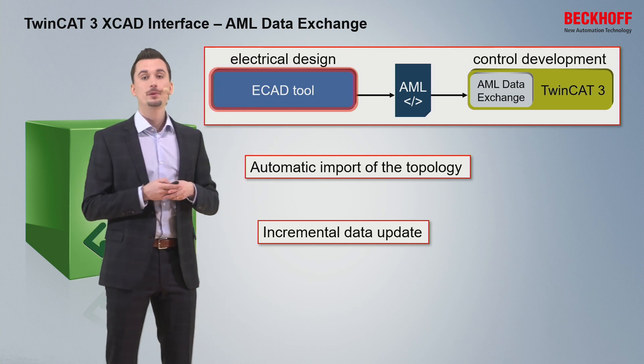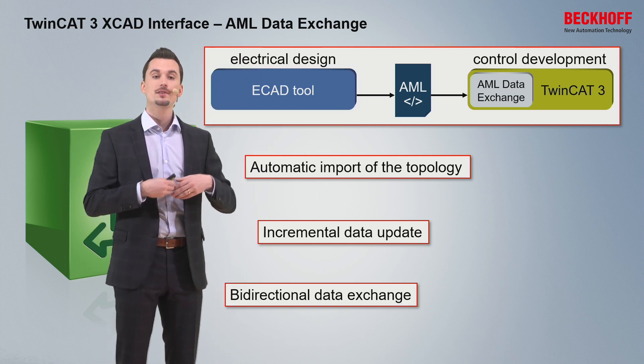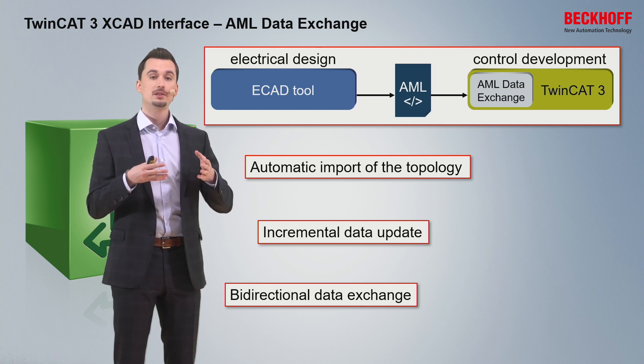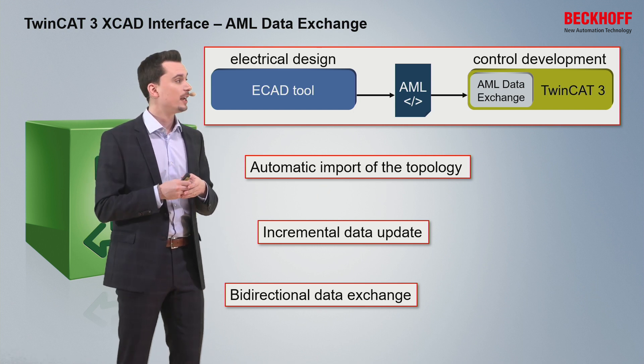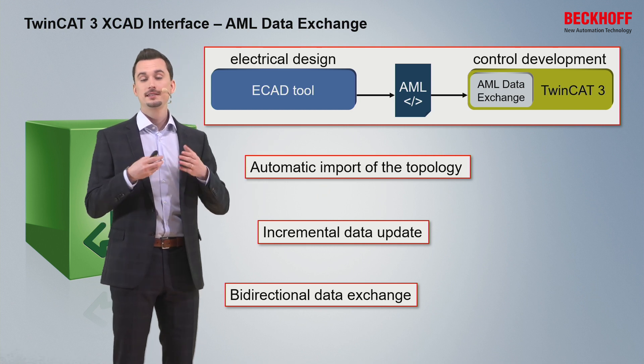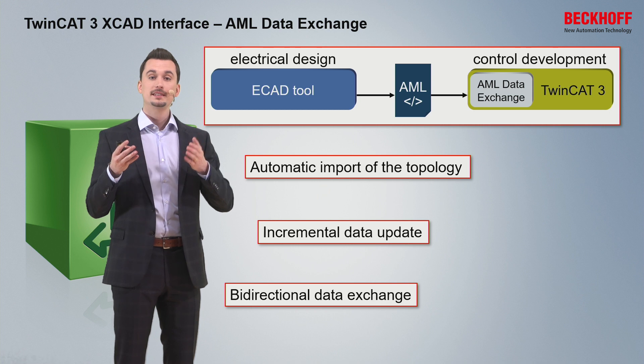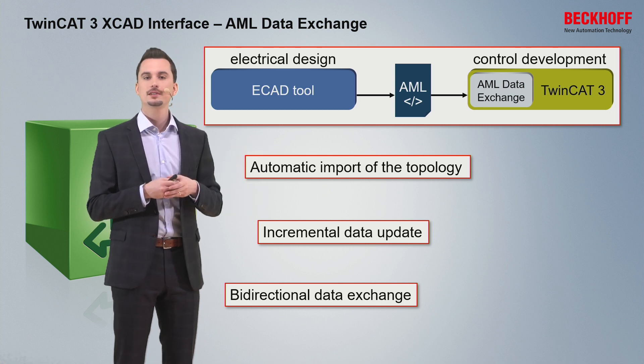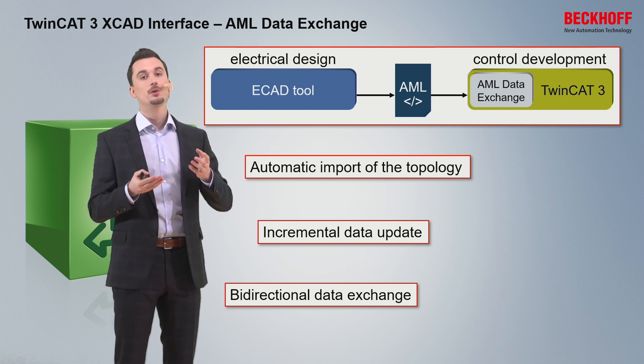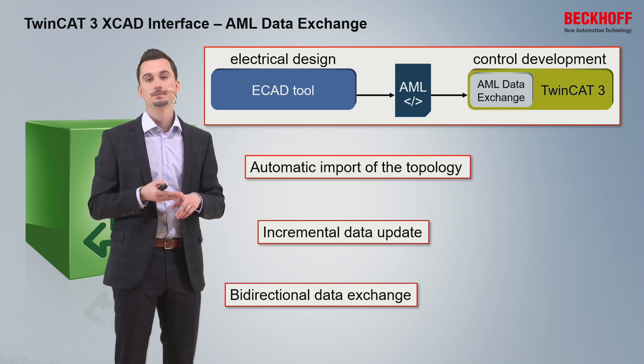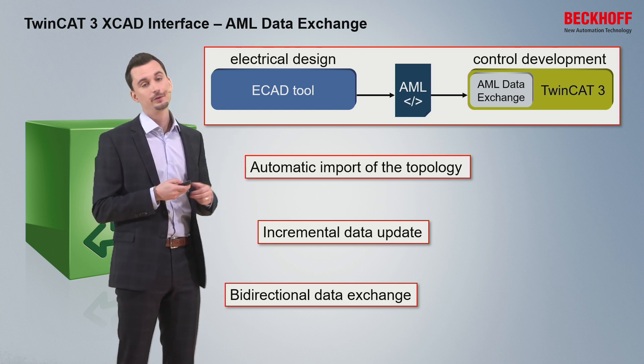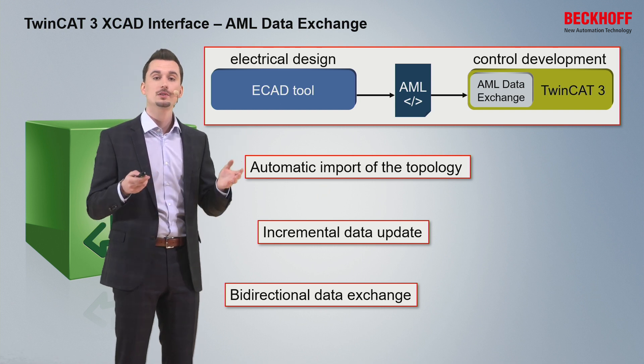At a later stage in your project, you can also use the bidirectional data exchange. For example, if you are doing commissioning and changing the IO topology on the TwinCAT 3 side, it is necessary to send those changes back to the ECAD tool side to update the electrical plan for documentation purposes and also in case of a service case. This is possible with the help of the AutomationML format and those unique IDs.